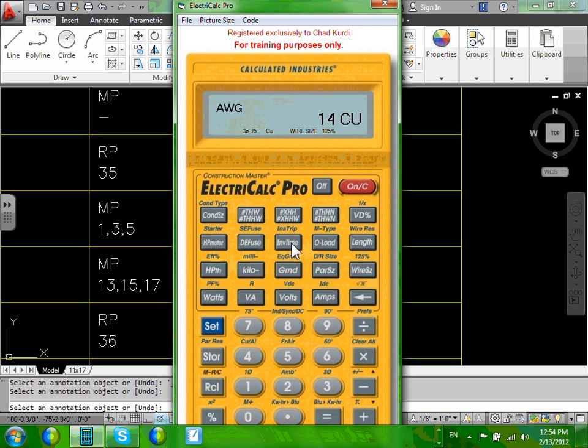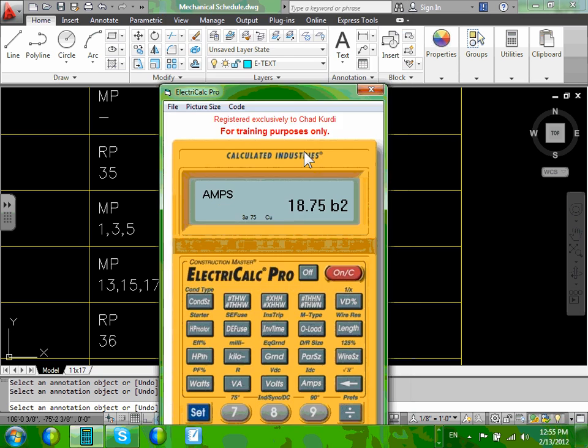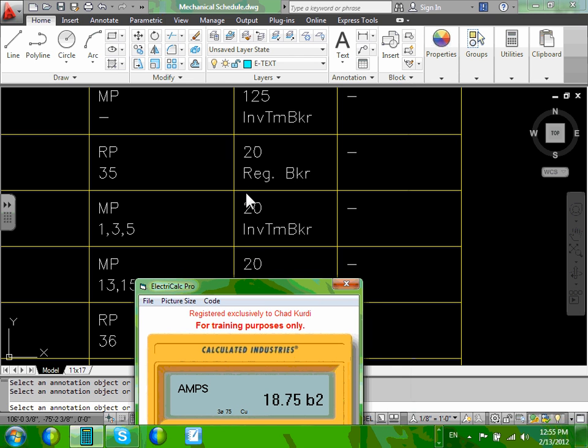I need the inverse time circuit breaker. Can you guys see what it says, inverse time circuit breaker? If you hit this, it gives you 18.75. If you hit it again, it will tell you what the multiplier is. Can you see what the multiplier is? 250 from the code. It's an inverse time circuit breaker, 250%. So this is the table, this is the multiplier, 18.75. You go to the next standard size, which is 20. So that's why my friend Dustin has gone to 20 here. 20. And what type? Inverse time circuit breaker.